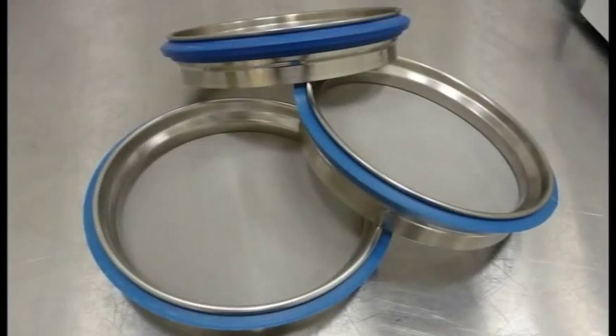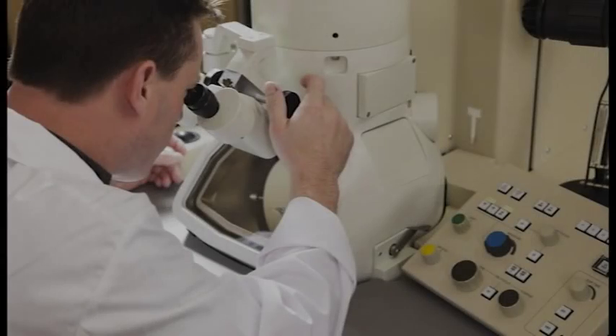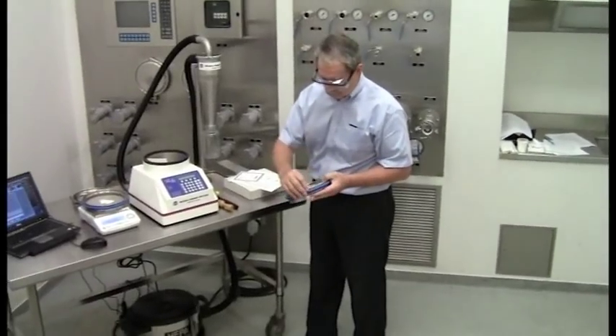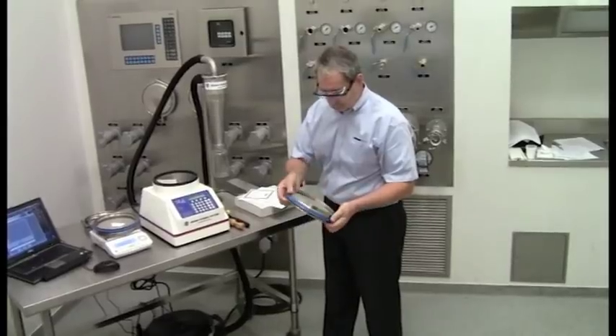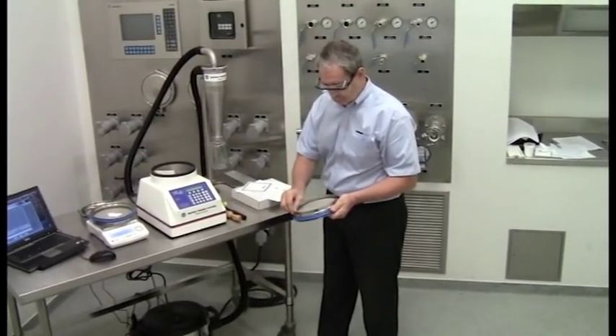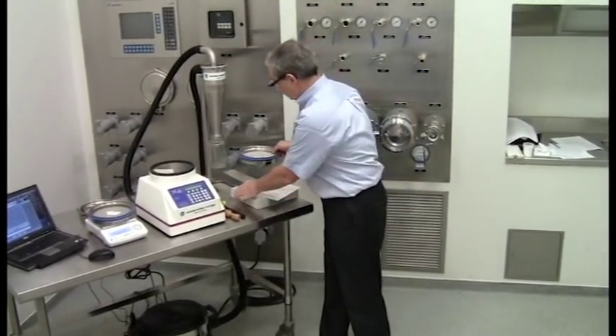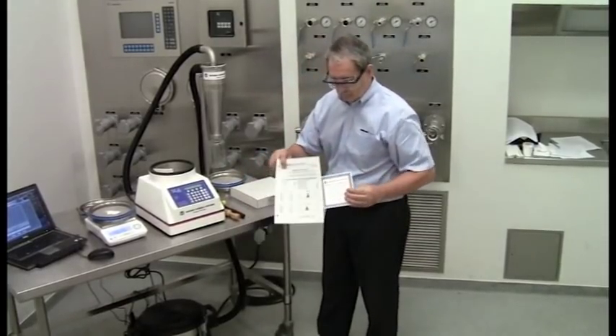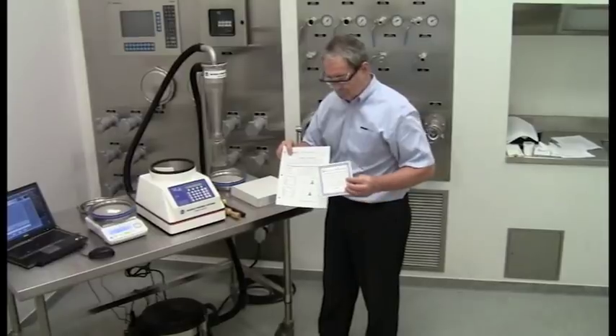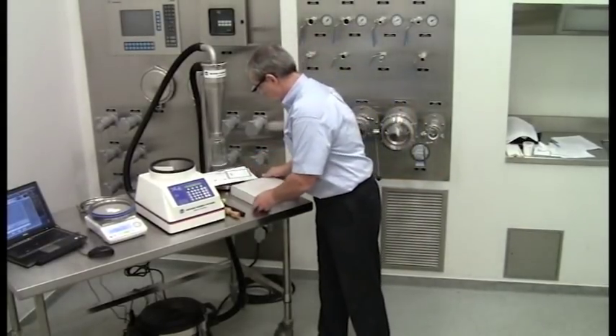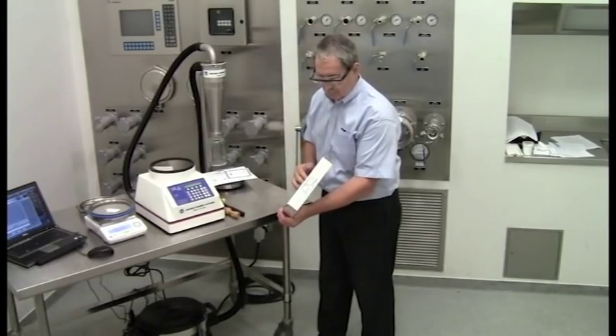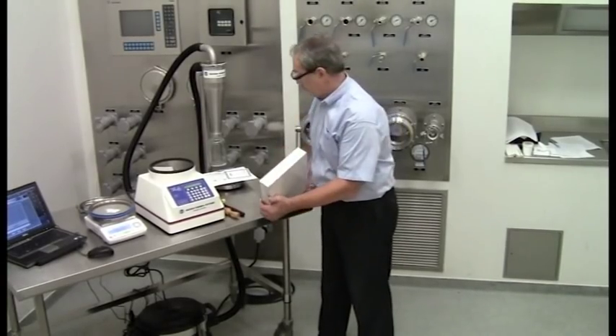Each test sieve has been designed in accordance with the current ASTM E11 inspection grade specification requiring the screen to be 99% accurate. The sieve screens constructed of stainless steel cloth and heavy duty 22 gauge frames are certified and supplied with verification histograms. They are individually boxed, shrink wrapped and bar coded for quick identification and easy inventory.